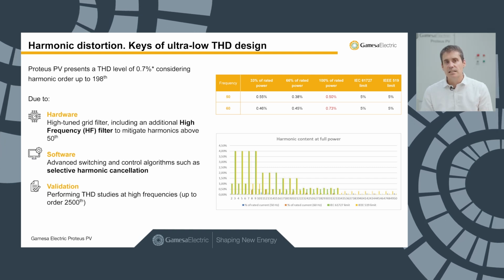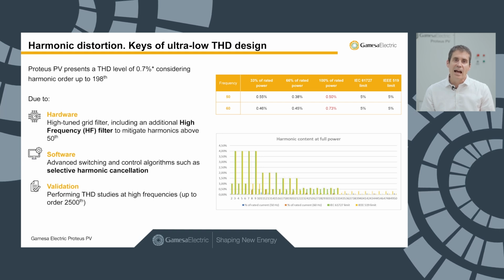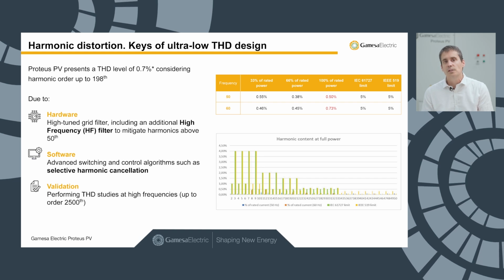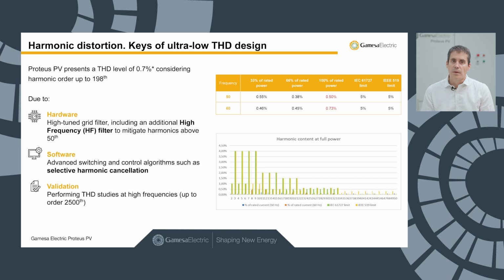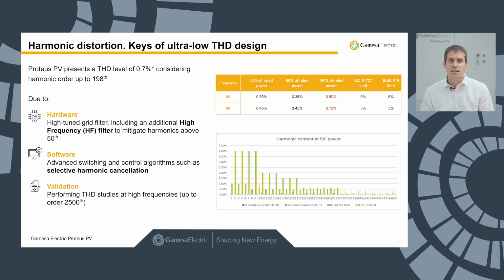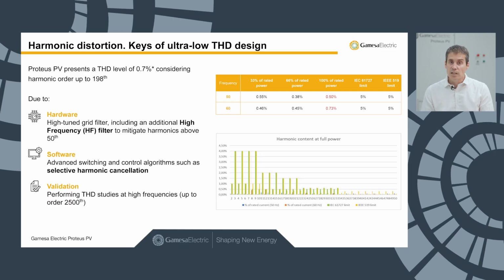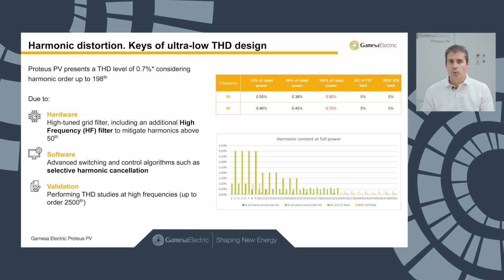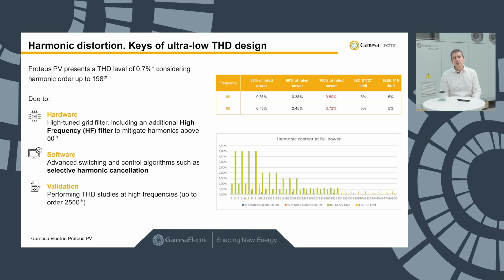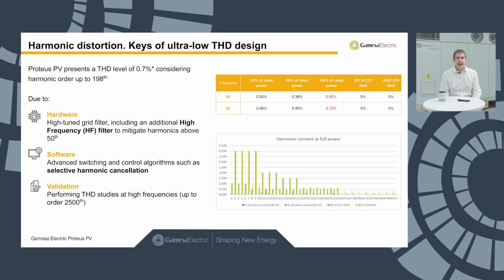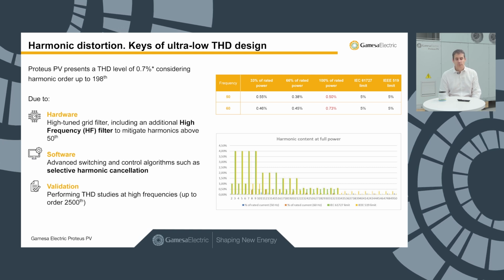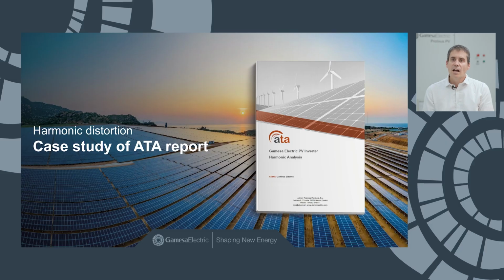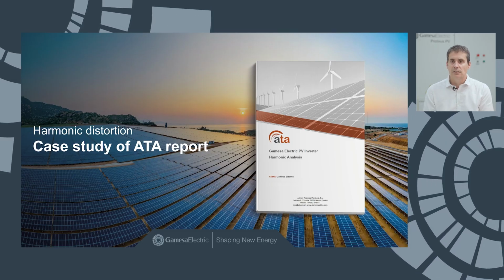Our inverters have a high-tuned filter, including an additional high-frequency filter to mitigate harmonics above 50th. We also use software, with advanced switching and control algorithms such as selective harmonic cancellation. And to prove that software and hardware are properly tuned, we perform validation campaigns, performing THD studies at high frequencies, taking into consideration up to the harmonic number 2500. As you can see in the table, our converters have a really low value of THDI. We will see how this affects the real world. We have performed a case study done by a third party, ATA, to prove that.